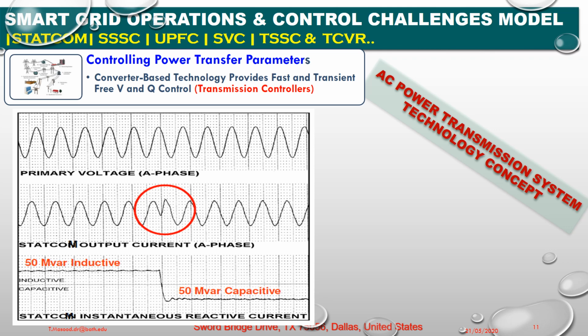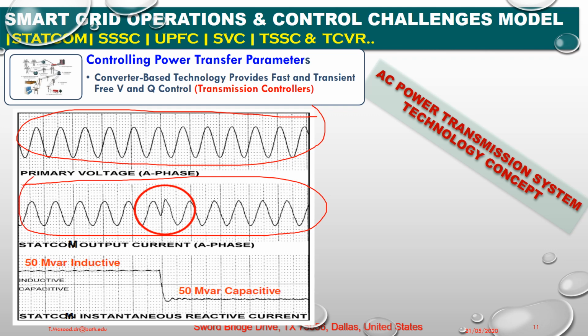Converter based technology provides fast and transient free V and Q control. If you see here, first, this is my primary voltage A phase, and second, the STATCOM output current at phase A, and in the third waveform you can see that before it was in inductor mode of operation, it turned into capacitor mode of operation when a transient happened. If you can see here in primary A, there is some deviation in this area, and the STATCOM diagnosed it and immediately turned from inductor mode of operation to capacitor mode of operation, and there is some variation in STATCOM output current here. So it immediately addressed the issue in this area, but it did not demonstrate any transient. So the converter based technology provides fast and transient free voltage and power control.